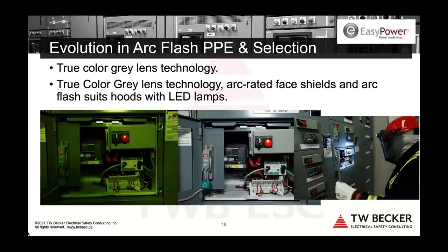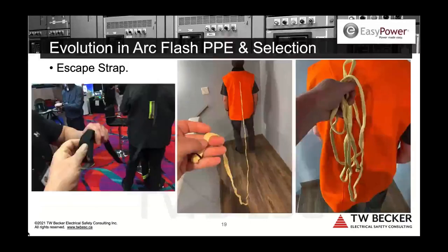This is the cool thing Jim mentioned, the escape strap. So again, this whole thing about rescuing, right, and being the first responder and how do I safely rescue. If there's a second worker, right, an electrical safety watch, this is a vest that you see on the right, and on the left, it's integrated into the arc flash suit jacket. This came out last year, all right? And I'm telling you, this is amazing stuff. We don't need the rescue hot stick anymore if we have this escape strap. So the vest goes over top of an everyday wear coverall or shirt, and then the arc flash suit jacket, well, that would be integrated into the arc flash suit jacket, all right?